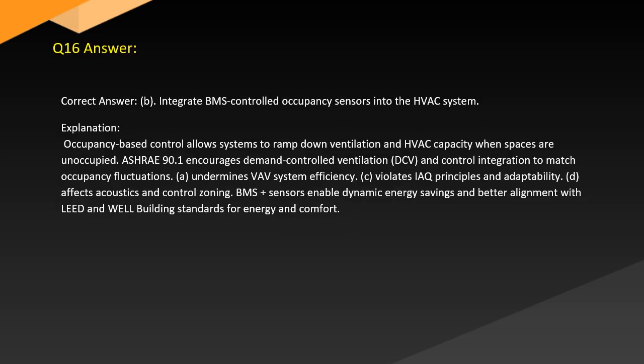Answer. Correct answer B. Integrate BMS controlled occupancy sensors into the HVAC system. Explanation. Occupancy-based control allows systems to ramp down ventilation and HVAC capacity when spaces are unoccupied. ASHRAE 90.1 encourages demand-controlled ventilation (DCV) and control integration to match occupancy fluctuations. A. Undermines VAV system efficiency. C. Violates IAQ principles and adaptability. D. Affects acoustics and control zoning. BMS plus sensors enable dynamic energy savings and better alignment with LEED and WELL building standards for energy and comfort.